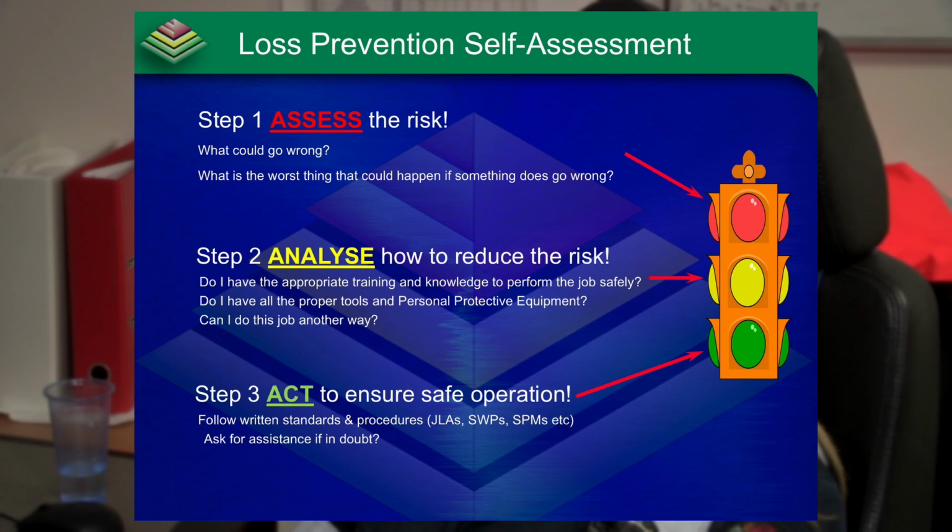Yes, I had that alarm up earlier and I had a discussion with the offsites panel. It's because of the ambient temperatures with it being a hot day outside. So tell me, what's the worst that can happen when that alarm's up? We have a high temp to the naphtha tank, it's an SOE. What's the process safety scenario that can occur as a result of that high temperature? It can lead to an excessive vapour build-up in the floating roof tank and it could sink the roof.